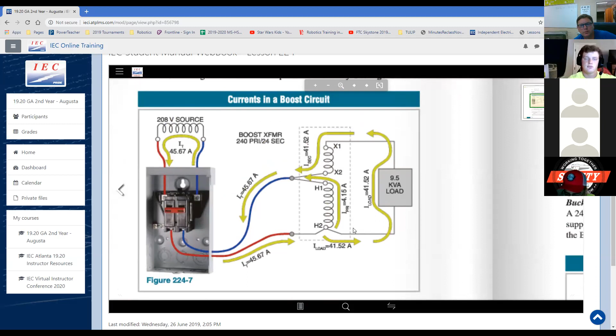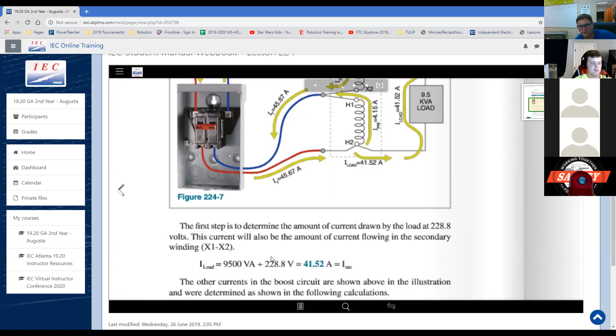Let's take a look at it. We've got 9,500 VA on our load, and we need to know our current for the load. I know it's already displayed, but how did they get that is what we're getting at. First we determine the amount of current drawn by the load, at 228.8 volts. This current will also be the amount flowing in the secondary winding.